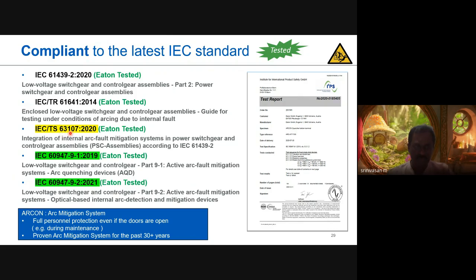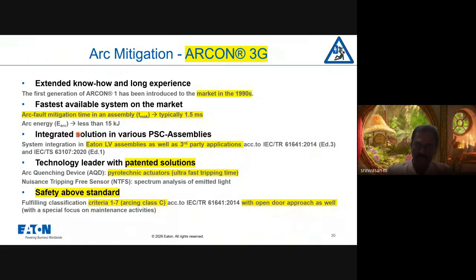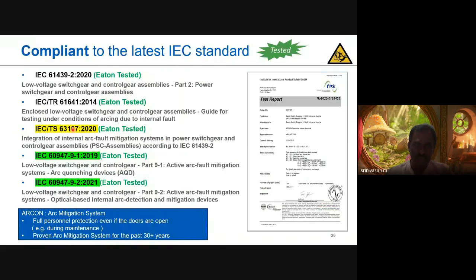Before jumping into that, I'll go over here. IEC 60947-9-1: the arc quenching device, ARCON, has been tested successfully as per this product standard. Also, the light sensor we are using for the arc mitigation system is type tested as per this standard. Then both the ARCON and the light sensor inside the switchboard have been tested for IEC 63107 also. So the complete switchgear, busbar, arc quenching device, ARCON and light sensor, all together, have been successfully tested as per IEC 63107.